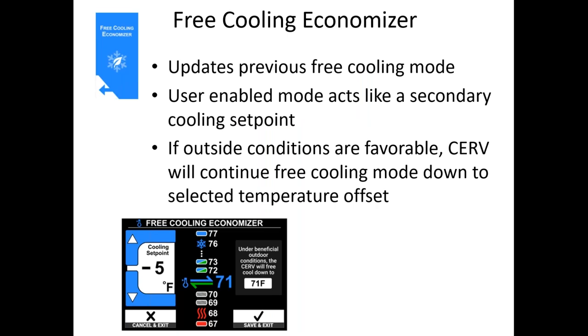So the free cooling economizer lets you do free cooling mode down to a secondary cooling set point. Previously, free cooling is something that the CERV would do automatically, but there are times when people want the CERV to do as much cooling as it can beyond what you may have set for the CERV's cooling set point. So that's what this does. You set an offset from your cooling set point, and anytime outside conditions are favorable to just bring that outside air in to help cool, it will use this set point automatically, so you don't have to do anything else. You can just have it look at what's going on inside versus outside, and then bring in that fresh air to help cool. Obviously, that will also be beneficial for air quality.